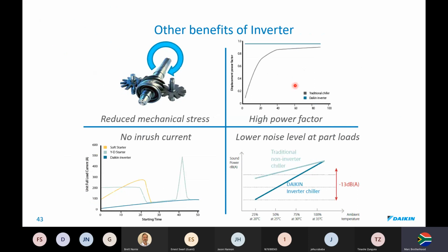So what are the other benefits of inverter technology? Well, first of all, this is what the Daikin technology looks like. We have a single screw with 2 gate rotors. They are 180 degrees mechanically out of phase with each other, purely to balance radial and axial forces. But besides that, with our inverter technology, there's reduced mechanical stress, as well as electromechanically. So on the bearings, there's not a lot of wear metals because you're not suddenly starting this from rest to 3000 RPM. You're gradually winding it up.